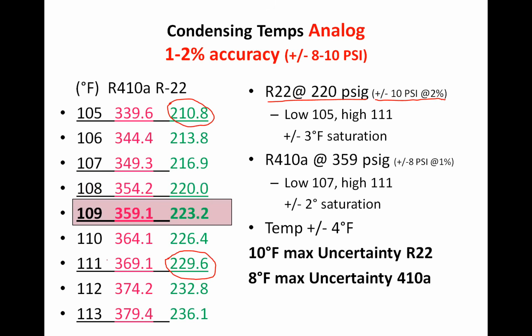If we look at 410A, right, and at 359 on there, now we're looking at a low of 107. Okay, so we're here, and we're looking at a high of 111, so we're right here. Again, we have a 2 degree swing, plus our uncertainty, so we're at 8 degrees total uncertainty for 410A. And again, we have all the same inherent problems.